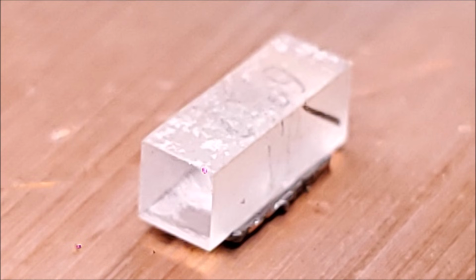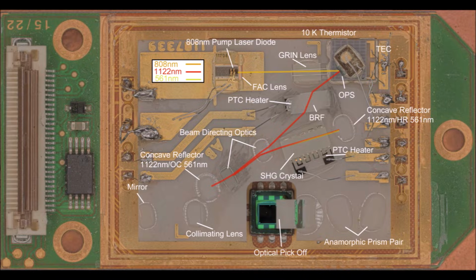on temperature. Second harmonic generation is typically done in an anisotropic crystal, such as potassium titanyl phosphate or lithium triborate. In this laser, temperature is key to controlling this process, which means non-critical phase matching is used. 561 nanometer laser light, produced by the nonlinear optical process of second harmonic generation, then travels through the output coupler, where it is then reflected, collimated by a lens, passed over the optical pickoff sensor, and corrected on the horizontal axes by two prisms arranged in what's called an anamorphic prism pair.